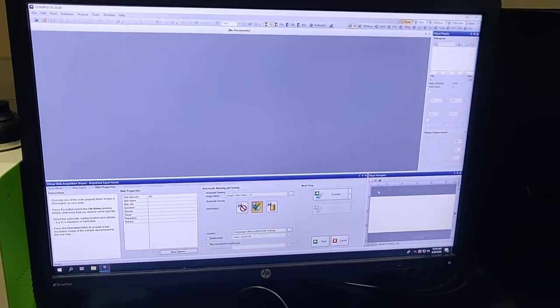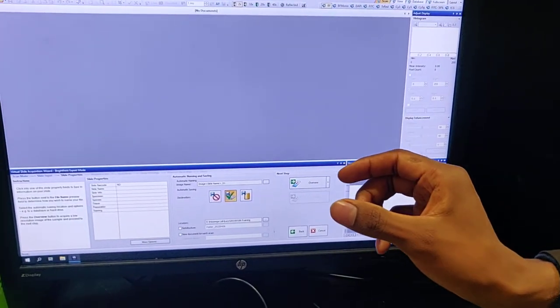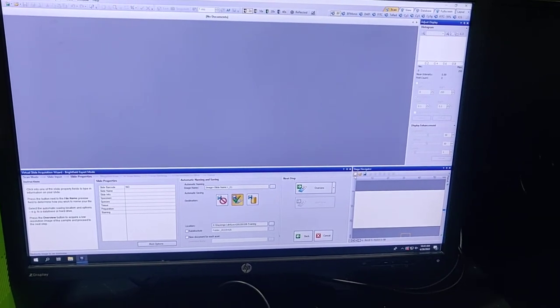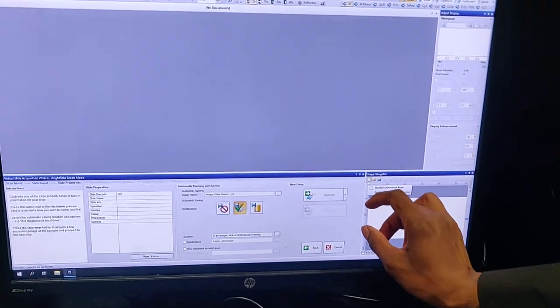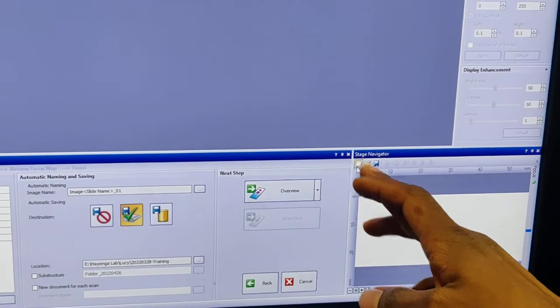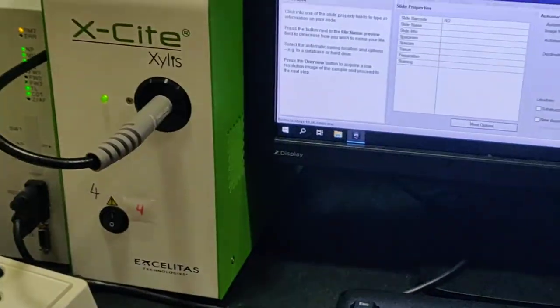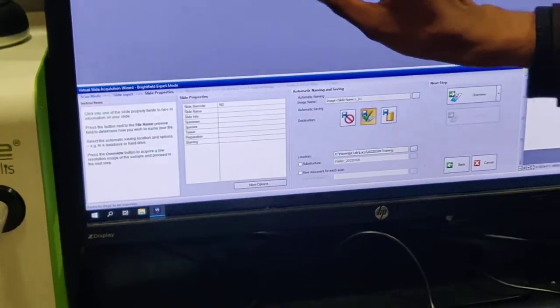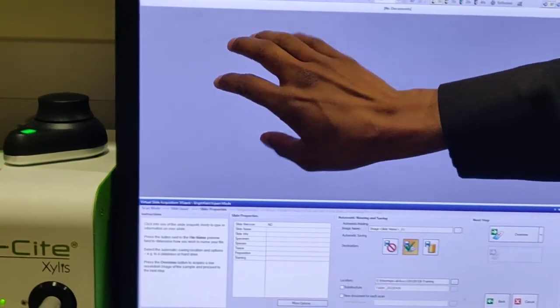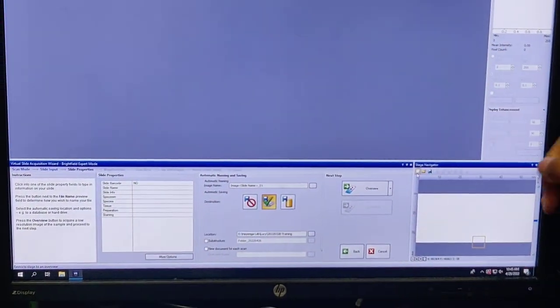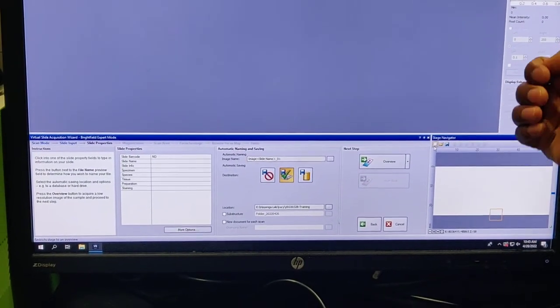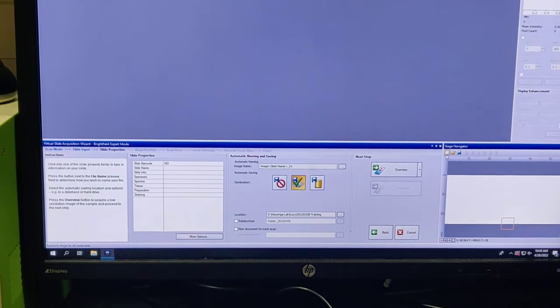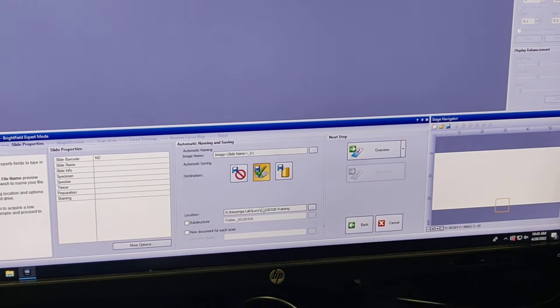When we are imaging, this should cover the entire coverslip area. If it is not, then we click this icon. It will allow me to define the overview area. If I click this, it will say take me to the top left corner. Using this joystick, I can move this thing under live mode. It will take me to the top corner. Then I say OK, it will put my top corner. And then it will say give me my bottom right corner. So you navigate and move it to the other end where you see that the coverslip ends. It's pretty self-explanatory.